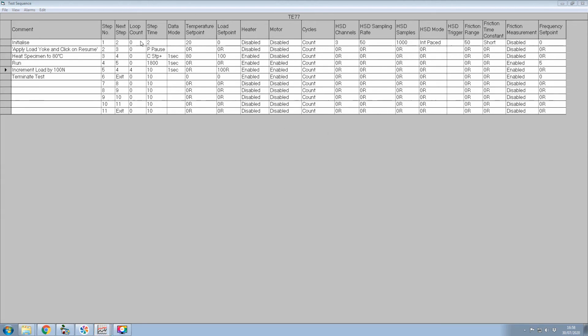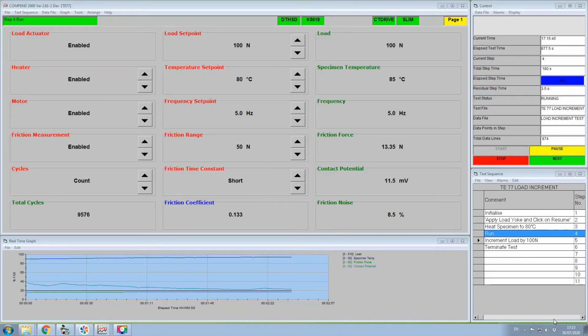With the load increasing each time the loop is executed, it is important to set the alarms for the steps within the loop to values appropriate for the maximum set point value achieved during the loops. If we now run the test, we can observe what happens on the real-time graph. We will of course have to rescale the graph to accommodate the changed test parameters.